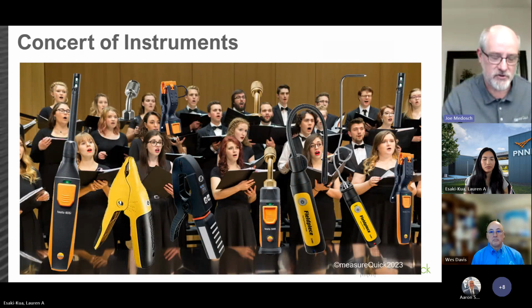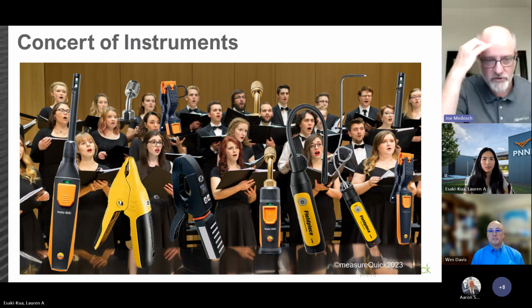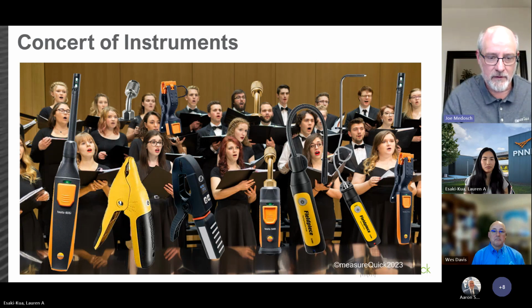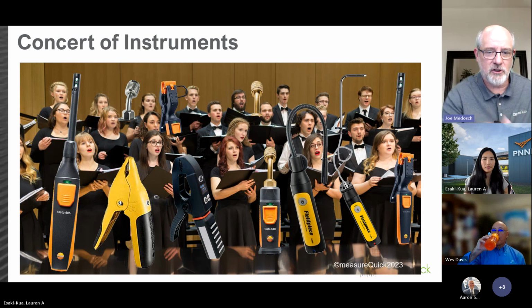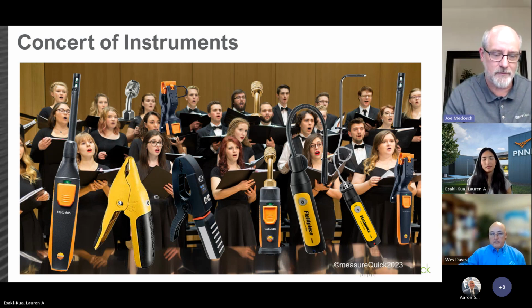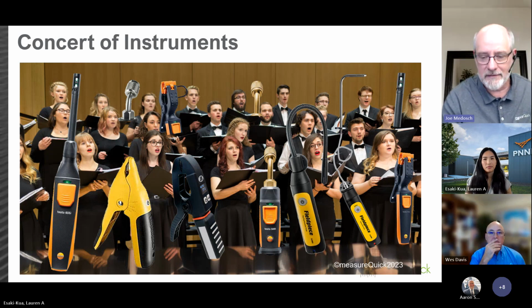So it is a concert of instruments. You can't just depend on one measurement and think you're going to be able to make conclusions. You've got to measure multiple things at the same time and relate them to each other. The temperature outside is crucial to how your refrigerant charge is working. Your temperature inside is crucial. Your static pressure, there isn't anything that really isn't crucial, but the goal is, if I'm not measuring them all simultaneously, I can't tell when one thing is failing. So you can't just share probes and move them around as you do measurements, trying to keep track of them and write them down. That's just a destiny for failure. So our goal is to use a lot of the stuff the industry has out there.